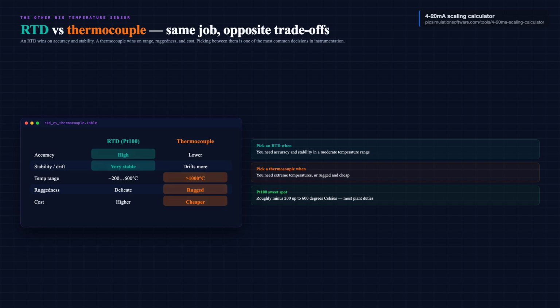So the rule of thumb is simple. Need accuracy and stability in a moderate range? Reach for a Pt100 RTD. Need extreme temperatures or rugged and cheap? A thermocouple. Picking between them is one of the most common decisions in instrumentation.